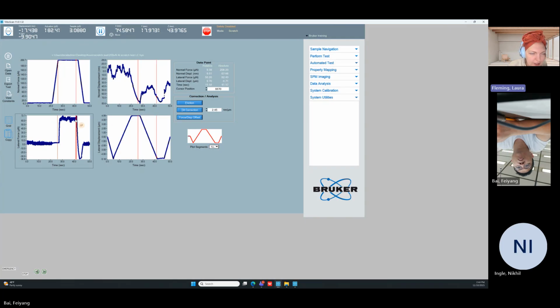So we're loading, and then we can look at the hold. So here's our scratch. We're holding in the normal, and we are measuring a pretty constant lateral force. As soon as we're loaded in, we're scratching. And this might have been low enough that we actually didn't cause any plastic deformation. This might actually be a pretty good friction test, but I would have to run more before I could definitively say that. I'm sorry, I'm struggling with these bars. There we go. So yeah, there's some normal displacement here where we load in, and then as soon as we start scratching, it pops up, which is a little bit strange.